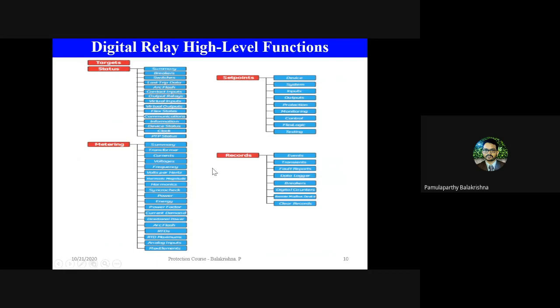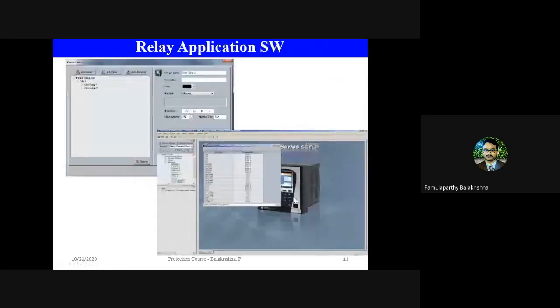Okay, so essentially, the combined binary status and analog information is used to execute the protection logic, and how the protection logic is executed is defined by the set points. All the records collected during various faults are used for the post-mortem or post-diagnostic analysis when a fault occurs. Okay, so these are the high-level functions of the digital relay.